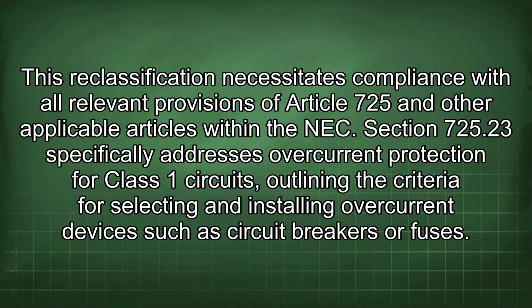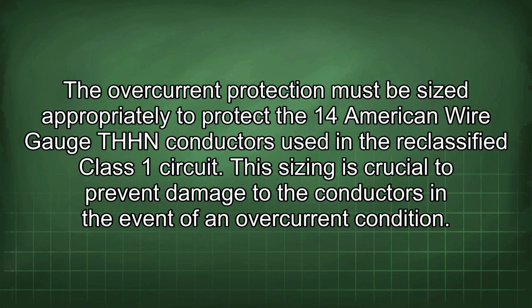Section 725.23 specifically addresses overcurrent protection for Class 1 circuits, outlining the criteria for selecting and installing overcurrent devices such as circuit breakers or fuses. The overcurrent protection must be sized appropriately to protect the 14 American wire gauge THHN conductors used in the reclassified Class 1 circuit. This sizing is crucial to prevent damage to the conductors in the event of an overcurrent condition.